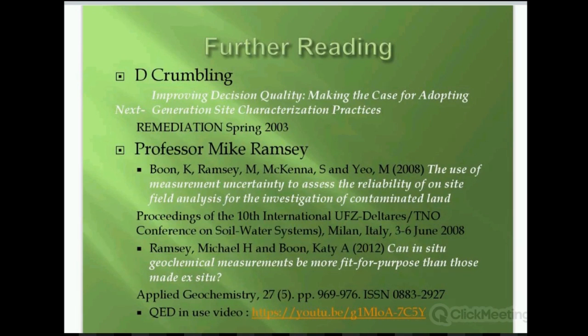And I see some have come through from Marianne. Can you download the raw data from the QED? Yes, you can. It comes out as an Excel file. Detection limits. The lowest detection limit for the QED, or the lowest concentration calibrator, what we use for quantification, is 5 parts per billion. The actual detection limit for most of the PAHs is 100 parts per trillion. Pretty impressive for a tiny little box.